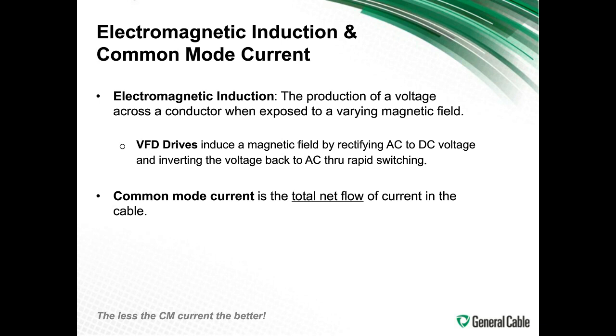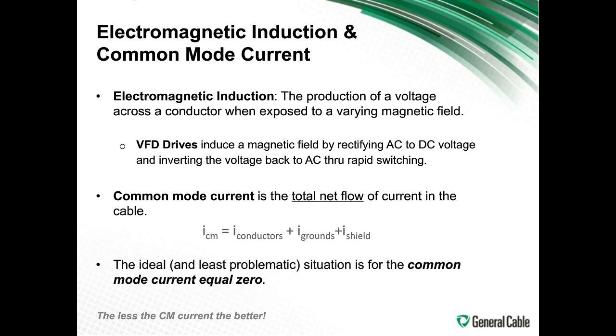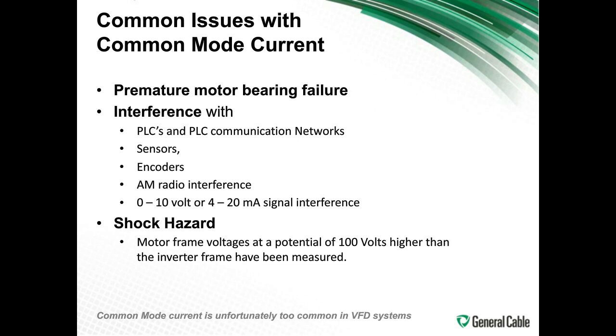Common mode current is the total net flow of current in the cable. Most of the time, you want this total net flow to be 0. And if you look here, it's the current that's in the conductors, in the ground, and in the shield. They all should equal 0 for the least problematic situation. However, that is not the case with high frequency modulation.